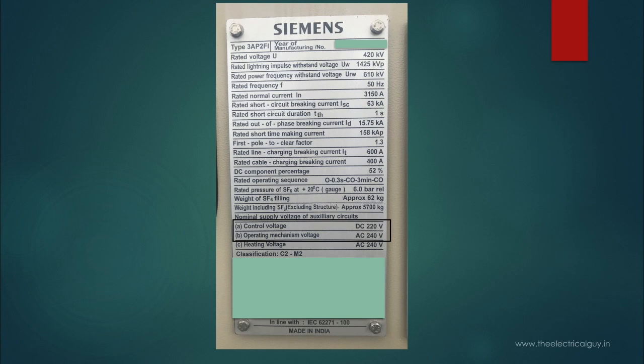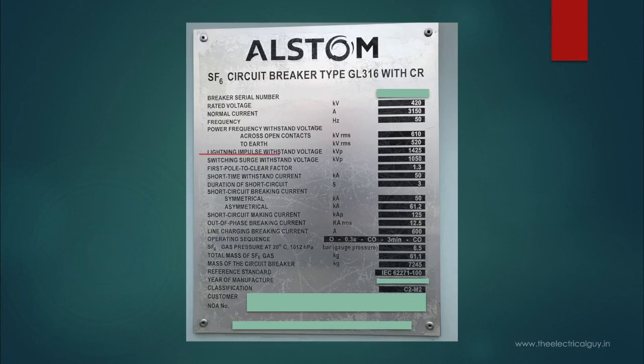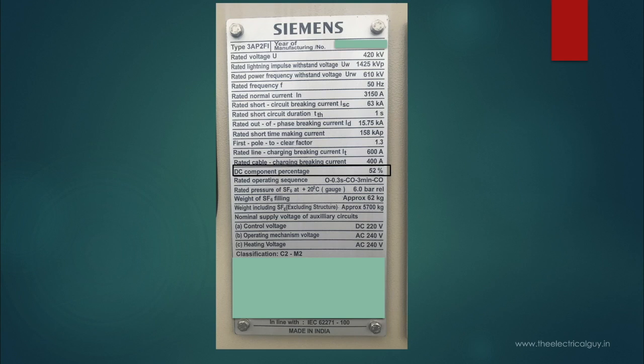Now the condition-based parameters. Rated switching impulse withstand voltage: switching surges generally occur above 245 kV voltage level, so this parameter is only found on circuit breakers above 245 kV. For the 400 kV voltage level, switching voltage is specified as 1050 kV peak, as you can see on the nameplate — this is also part of the basic insulation level. DC component of short circuit current: if the DC component exceeds 20% at the time of contact separation, it must be shown on the nameplate.